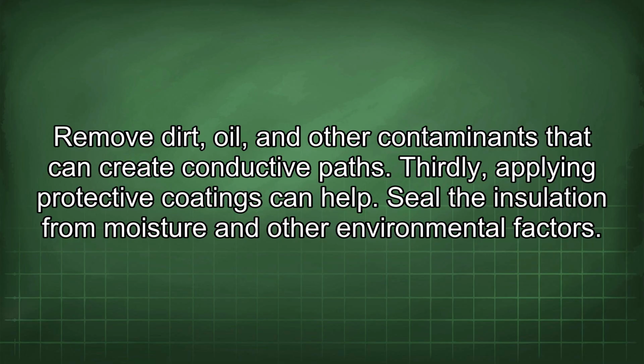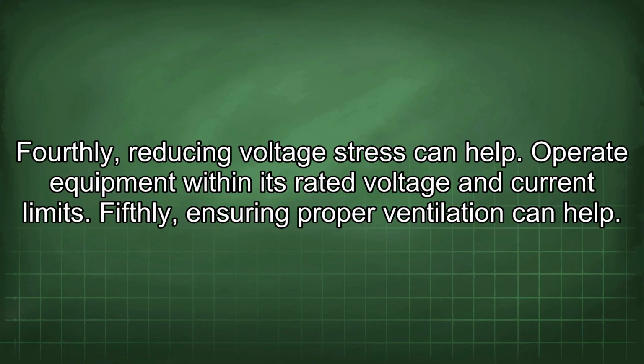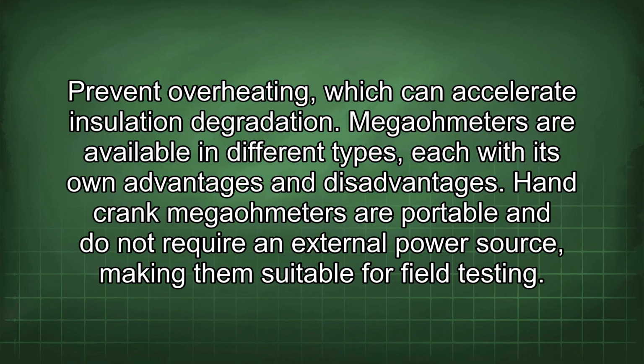Thirdly, applying protective coatings can help. Seal the insulation from moisture and other environmental factors. Fourthly, reducing voltage stress can help. Operate equipment within its rated voltage and current limits. Fifthly, ensuring proper ventilation can help. Prevent overheating, which can accelerate insulation degradation.